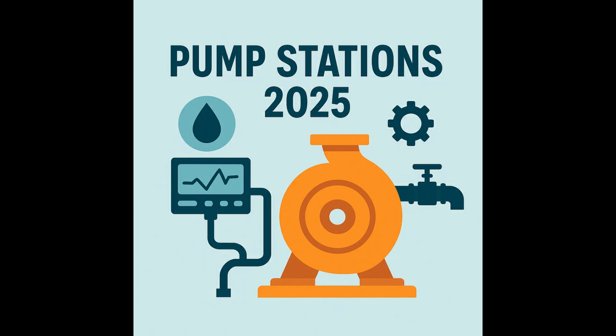The second step, once you've defined that operating envelope, is evaluate pump selection. You have to match the envelope with the right pump hardware. Right. That means choosing the right type: centrifugal, submersible, vertical turbine, whatever fits the application. It means getting the right motor speed and horsepower, and importantly, selecting the right impeller size and trim, because that actually shapes the pump's efficiency curve. Yeah. Proper selection ensures the pump actually operates inside its POR under most, if not all, normal flow conditions. Like you said before, you wouldn't buy a race car if your commute is all stop-and-go city traffic. Right. Pick the right tool for the specific job.